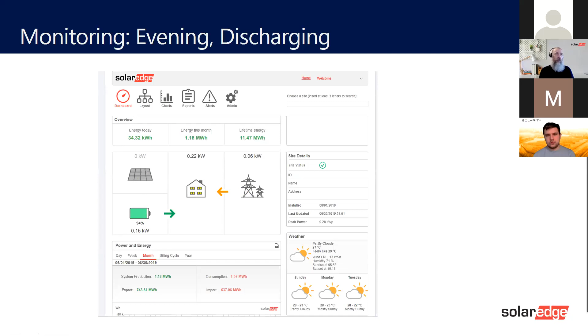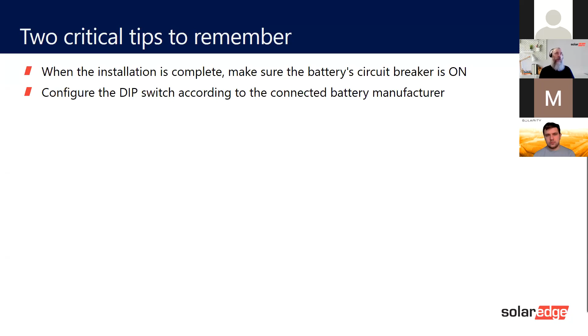So what you need to pay attention to: when your installation is complete, check that the safety switch is switched on. Remember, BYD and LG have different switch positions on different batteries - BYD is up, LG is down. Here it's marked which manufacturer goes up and which goes down.